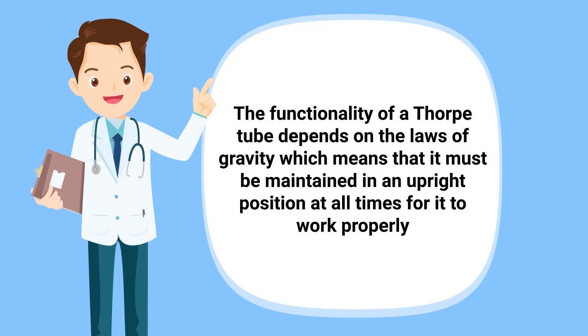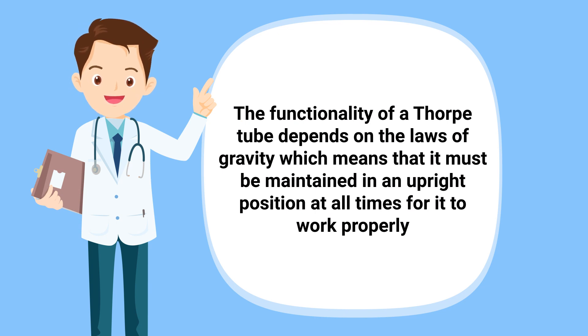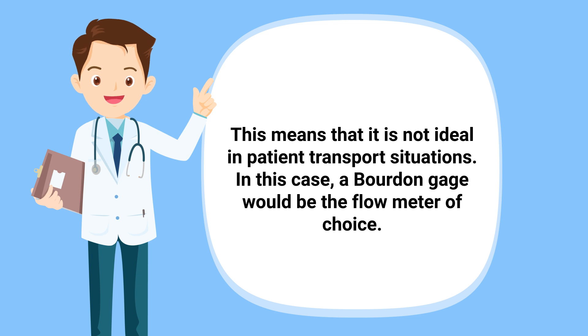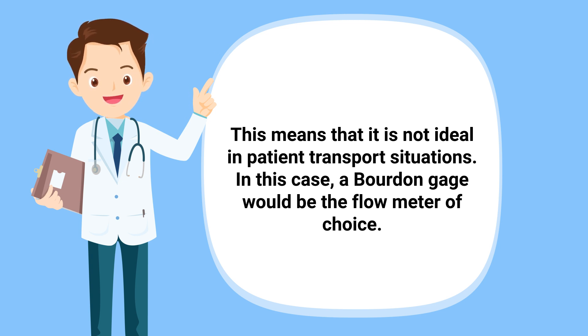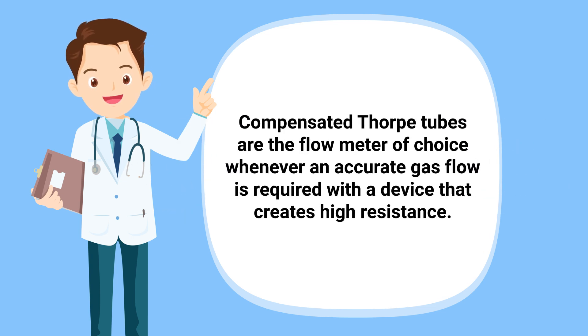The functionality of a thorpe tube depends on the laws of gravity, which means that it must be maintained in an upright position at all times for it to work properly. This means that it is not ideal in patient transport situations. In that case, a bourdon gauge would be the flow meter of choice, which is a topic covered in a separate video on our channel.